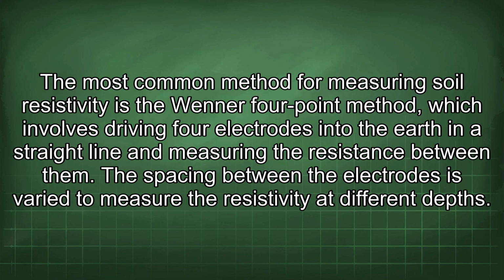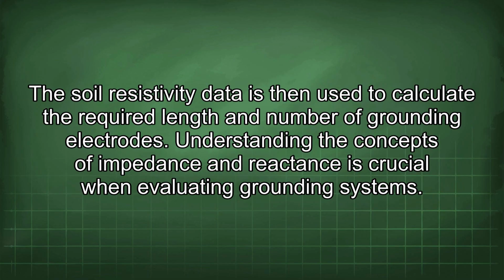The most common method for measuring soil resistivity is the Wenner 4-point method, which involves driving 4 electrodes into the earth in a straight line and measuring the resistance between them. The spacing between the electrodes is varied to measure the resistivity at different depths. The soil resistivity data is then used to calculate the required length and number of grounding electrodes.